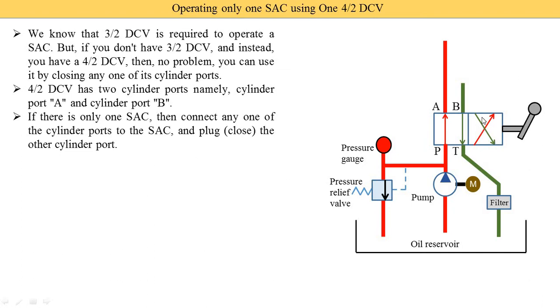Suppose we use this 4/2 DCV — we are able to connect two single acting cylinders, where A port connects to cylinder A and B port connects to cylinder B. But here we have only one single acting cylinder, so we have the option to either block port A or block port B. Here we block the B connection port — you see the sign of the cross. No oil is supplied from port B to the hydraulic system because it is blocked.